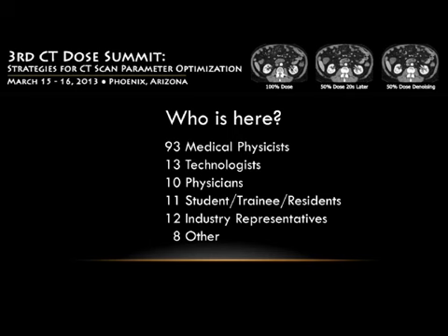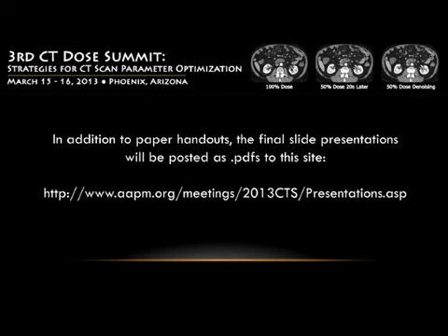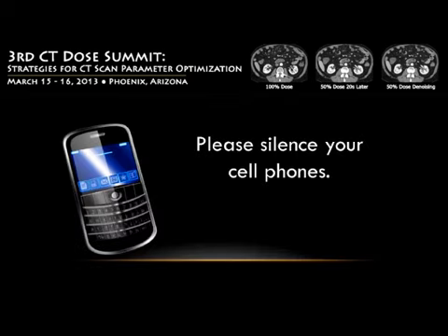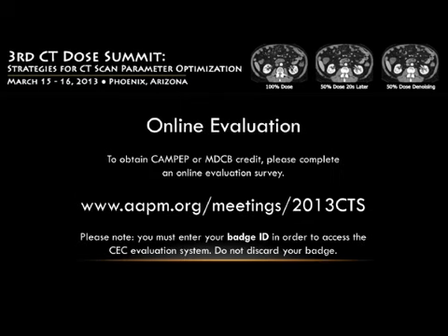When you scan the pelvic part of that phantom, did your graphic prescription continue on down, or did you strictly prescribe down there where there was no SCOUT? Prescribed where there was no SCOUT. Okay. So when you prescribe when there's no SCOUT, yes, it uses the minimum MA. However, if you continue on off of the SCOUT, the system uses the last known MA rotation. Okay.